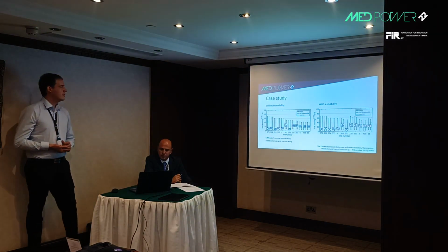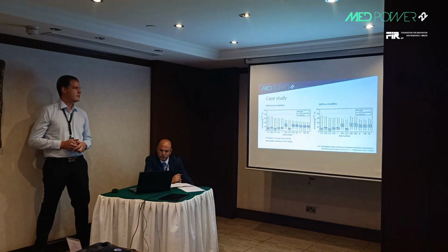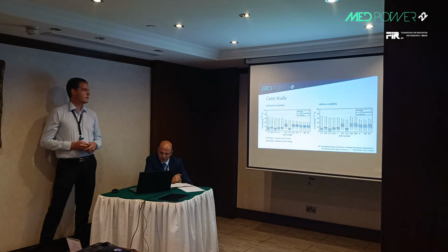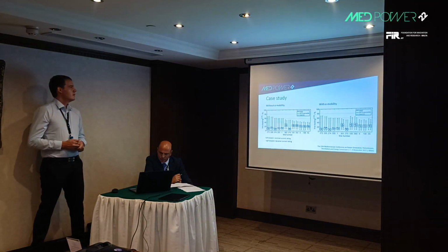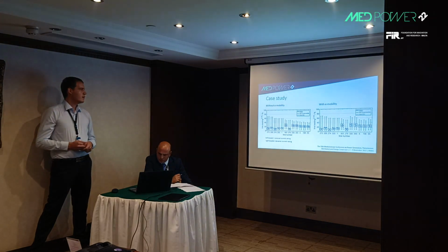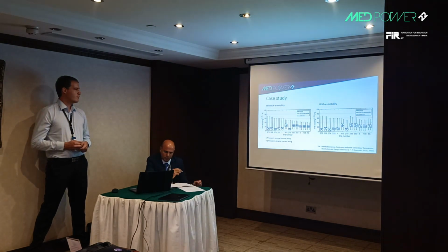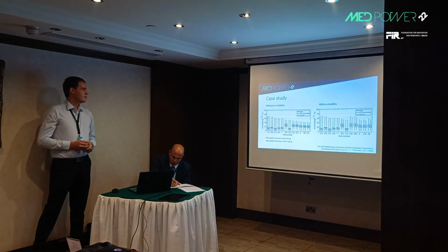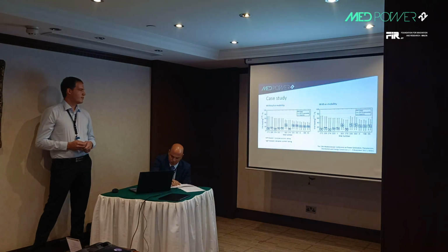And now we see here the results for one grid. It's a load-dominated grid. I have another grid with more renewable energy sources, but you can find it in the paper. On the left side, we have without e-mobility, and on the right with e-mobility. And the left box plots are with the nominal current rating, and the right box plots with the dynamic current rating. And you can see that for both, the transmission capacity increases.